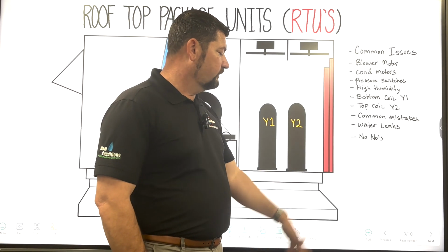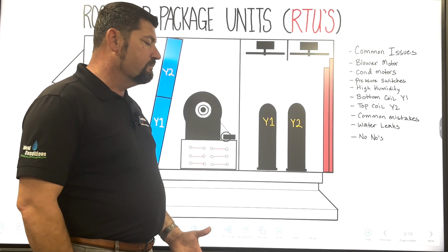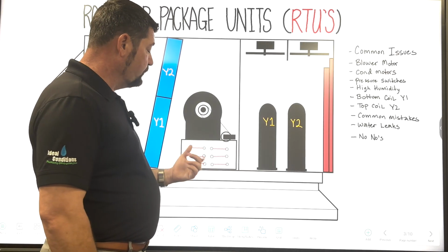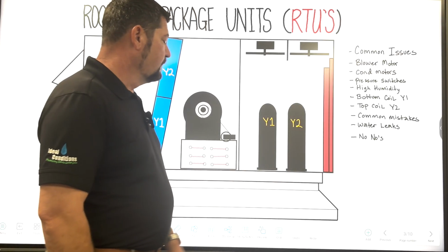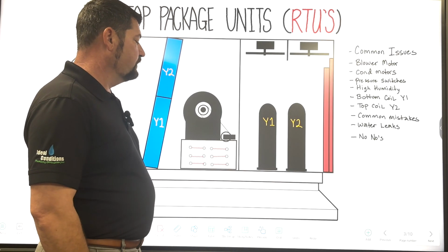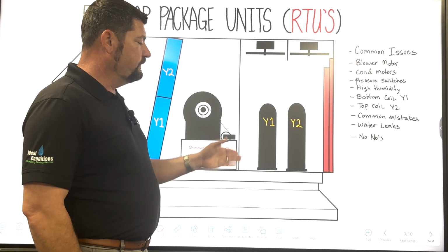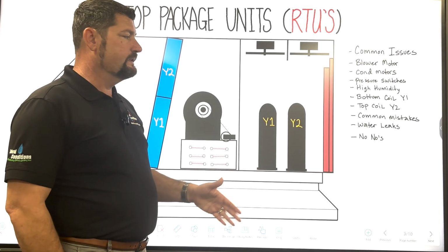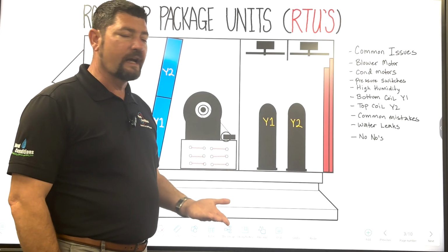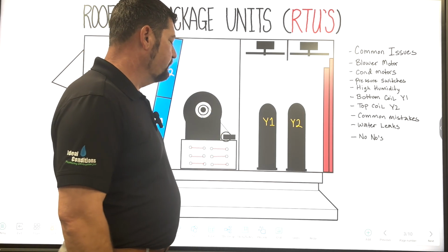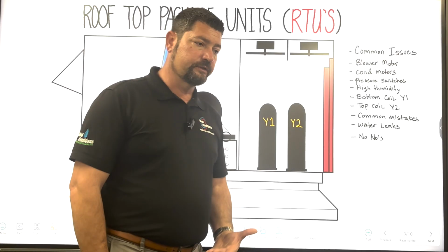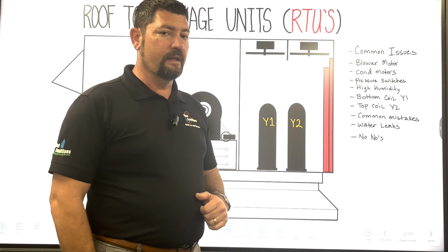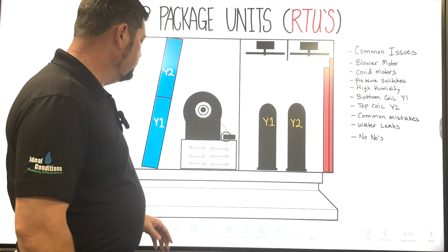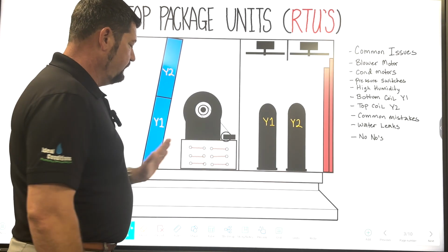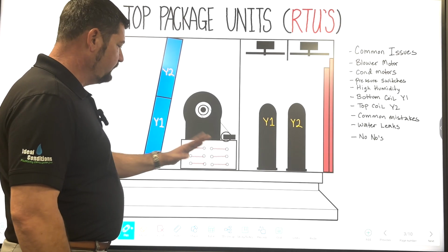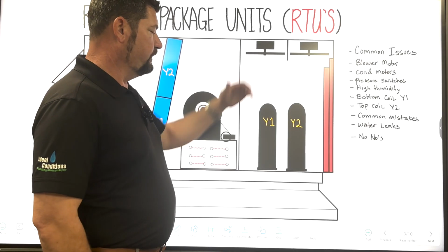Water leaks. These things are known for water leaks, and they're known to be misdiagnosed on those water leaks. As I mentioned earlier, somebody can just step on a screw and it can be a roof leak. The curb can be leaking if the unit's not sitting correctly on the curb. If the unit has been drilled into, meaning the base plate of the unit has been compromised, then it's not going to have the integrity that it was designed to keep water out. Water will now intrude inside the building through those holes. So you may just need to put a little bit more silicone in the area that somebody brought an electrical whip up in. If you're going to bring an electrical whip or low voltage wires up in these things, you have an entire blower cavity that you can access perfectly fine, and then from there you can actually get into the control panel.